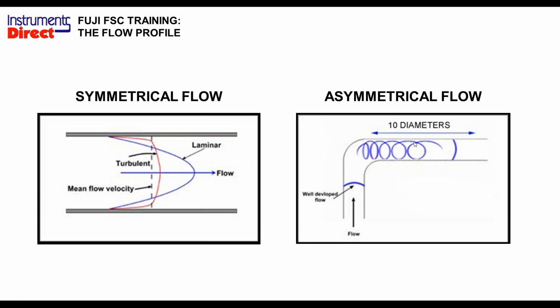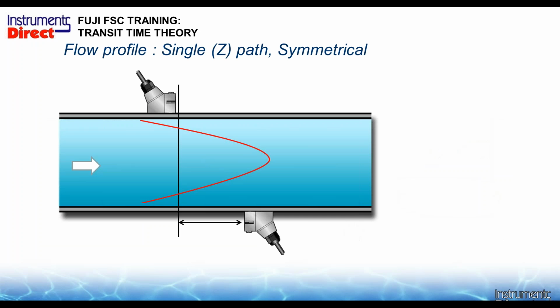As you move farther down the stream, you may eventually pick it up, but it'll be bobbling around, so it won't be a very stable reading, and you may have to profile a pipe to get it to work. But when you get down to 10 pipe diameters, everything will be great. So optimum performance, 15 pipe diameters or 10 plus 5, is the perfect situation. Lower flow rate, less straight run of pipe. Higher flow rate, more straight run of pipe. Major obstruction, more straight run of pipe. If you have a valve or something invasive in the line there, a pump, you need to get farther downstream.